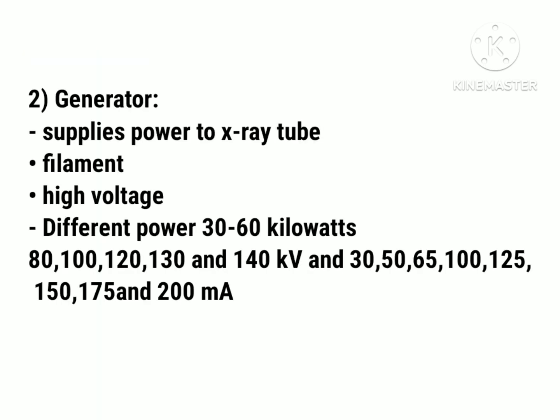The second component of the gantry is the generator, which is present inside it and supplies power to the x-ray tube so that the x-ray tube can produce electrons needed to produce x-ray photons. The power supply is provided to the filament of the x-ray tube so that the filament can produce high-energy electrons which get accelerated towards the anode, where x-ray photons are produced. The power supply of the generator is 30 to 60 kilowatts, and the exposure techniques range from 80 to 140 kilovolts and 30 to 200 milliamperes.